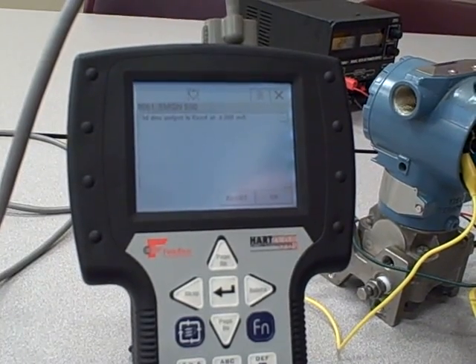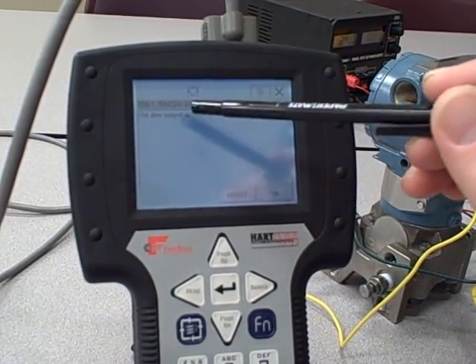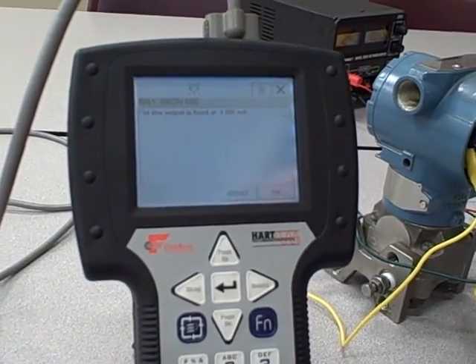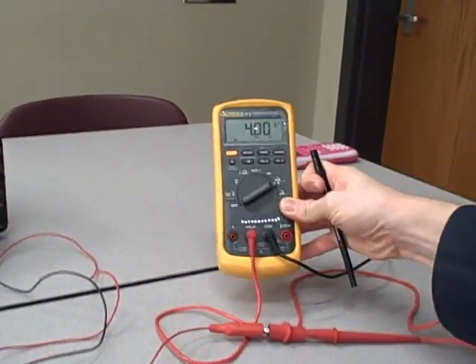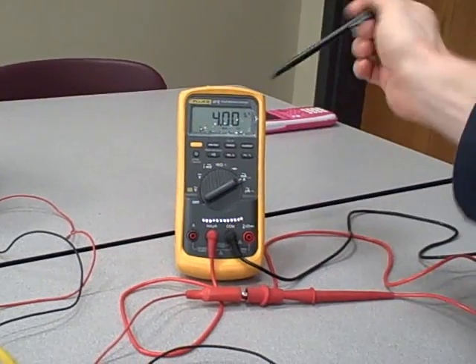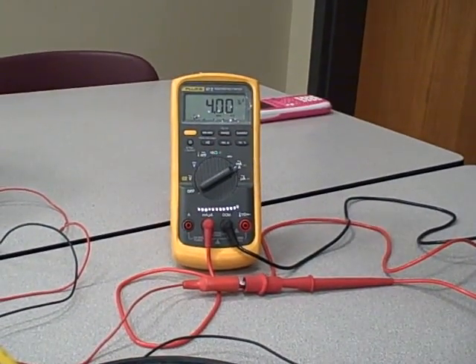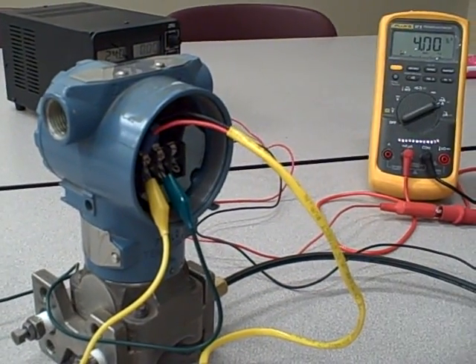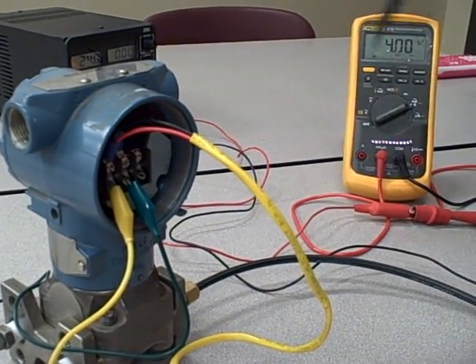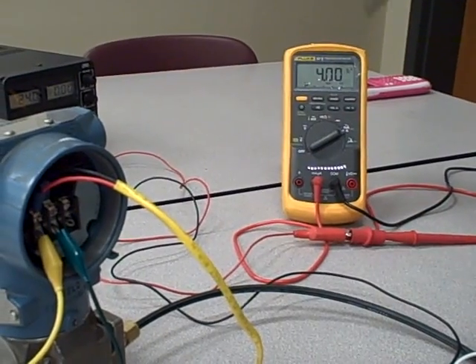For example, I'll tell it to go to 4 milliamps. It says here, field device output is fixed at 4 milliamps. If we look at our loop current meter, we see that the current is now fixed at 4 milliamps. This is despite the fact we still have about 500 inches of water column pressure applied to the transmitter. It is now ignoring that applied pressure and fixing the output at 4 milliamps.